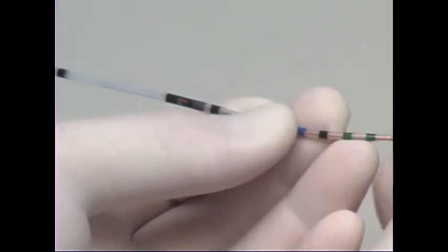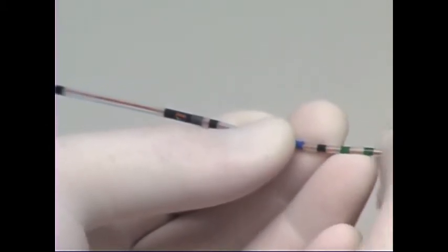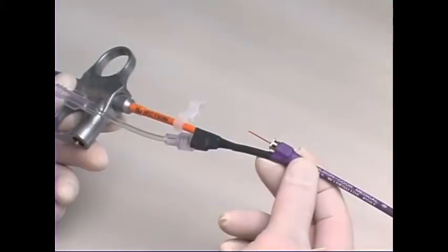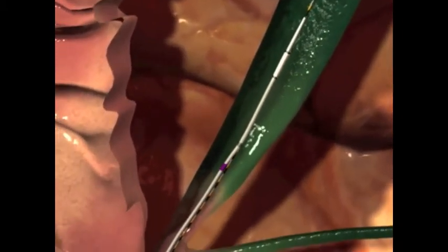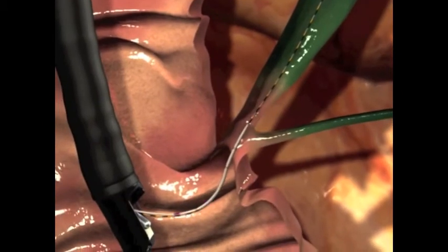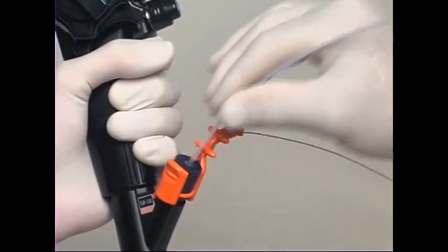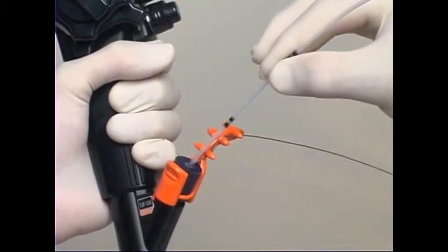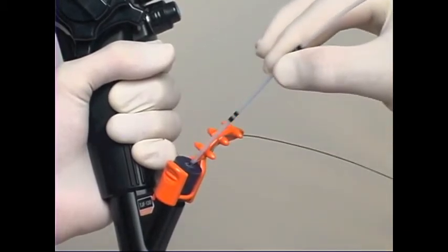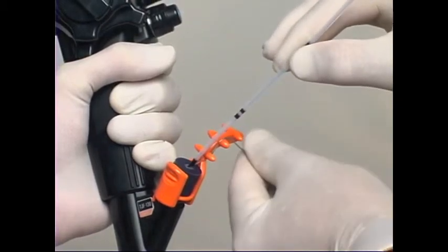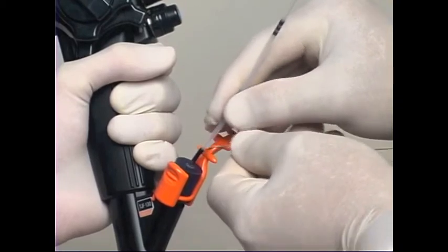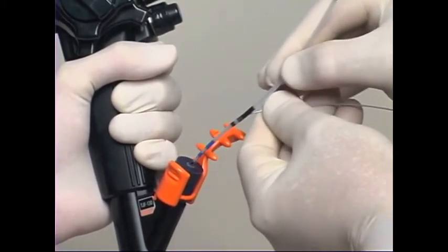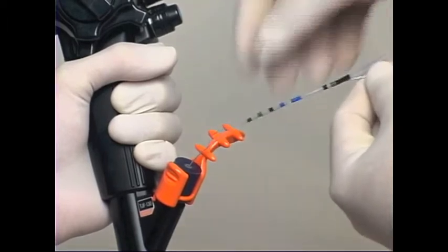When backloading over a long wire, place the wire through the end of the catheter. Bypass the IDE port and advance the wire guide until it exits the proximal wire port. Regardless of which length wire you are using, if intraductal exchange is not required, Fusion devices can zip freely over any length wire, providing incomparable speed and efficiency. When using the zip technique, when the device reaches the wire guide locking device and resistance is felt, simply perform a mini exchange. Unlock the wire guide, zip the device out of the way and reattach the wire guide.